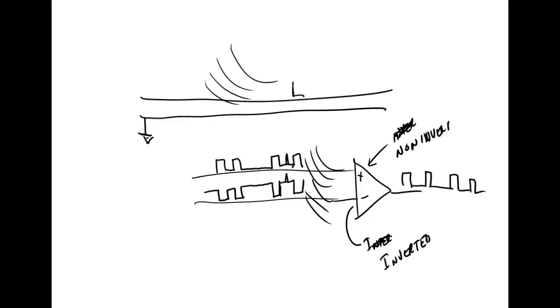So that means I don't have to use shielded wire anymore, right? Y'all understand? Because now the system itself rejects common mode signals. It allows us to use lower voltage levels, so we have almost no current flow at all, which means these don't radiate much signal, and it allows us to send these things at real high speeds.